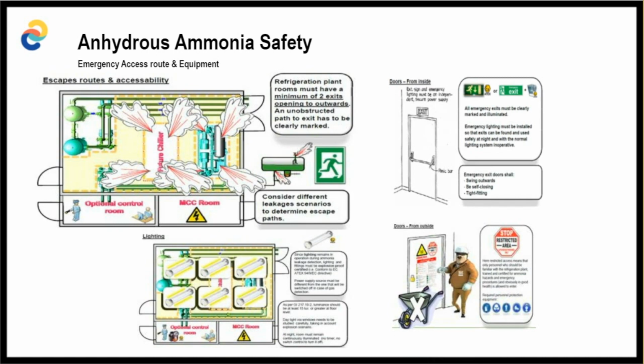For this slide, all equipment shall be located in such a manner as to allow enough space to exit in the event of an emergency. Emergency exits must be clearly marked and illuminated. No obstruction should be located in these exits. Also, based on the code, the machinery room shall be equipped with light fixtures delivering a minimum of 320 lumens per square meter.